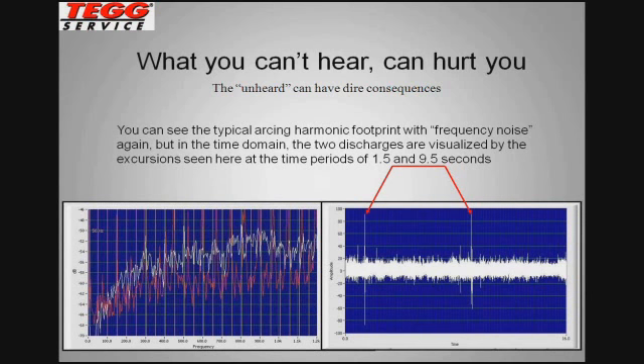Based on this analysis, we recommended the customer do a few other things because we knew we had early stages of insulation breakdown within this liquid-filled transformer. And they're not as easily replaced or readily available today as they used to be in the past. So you want to catch items like this early. This transformer was at a college campus, and it was in a high-activity area. So the customer did not want to see the transformer fail, and we came up with an action plan to monitor this. Would I suggest shutting the transformer down based on this find and replacing it? No, I would not. There are some other steps that we could take because it does indicate breakdown internally.